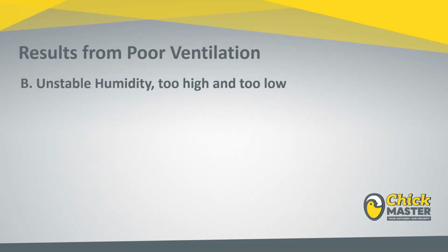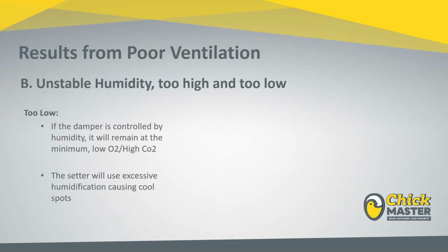When we look at unstable humidity, too high and too low, if the damper is controlled by humidity, obviously it will remain at minimum, which is going to reduce your oxygen and going to produce higher CO2 readings. The setter will use excessive humidification, causing cool spots.